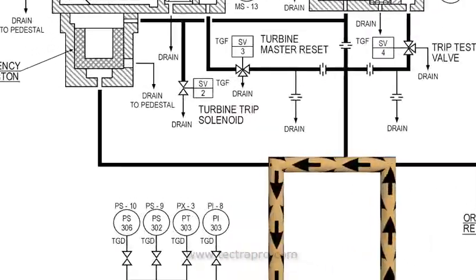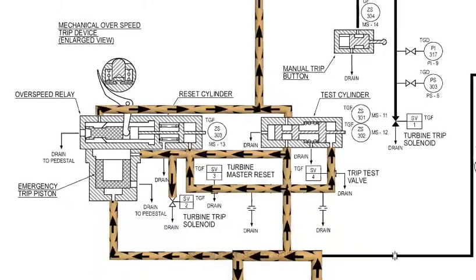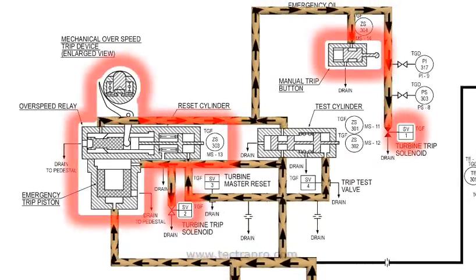Emergency oil leads to a trip by either the mechanical overspeed trip device, a manual trip, or a solenoid-activated trip.